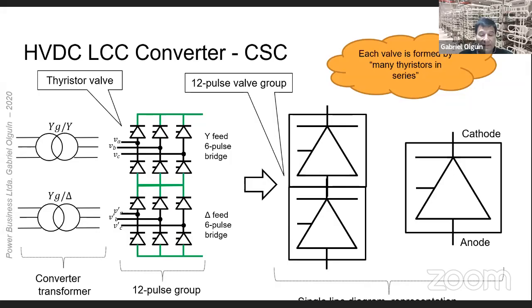So HVDC LCC is a current source converter. The fundamental building block of the HVDC LCC converter is the controlled 6-pulse converter. However, in HVDC applications, the current practice is to use a 12-pulse converter, which is built by connecting two 6-pulse converters in series on the DC side, fed by two converter transformers that introduce a 30-degree phase shift in phase voltages. In a single line diagram, this is usually shown in this way, or eventually with only one converter, but in practice it is a 12-pulse converter. We will see how the converter works in a few slides.